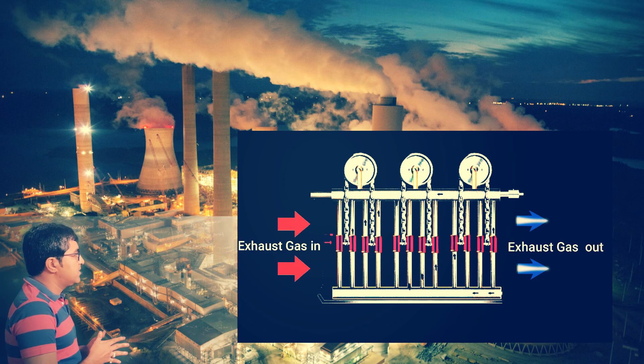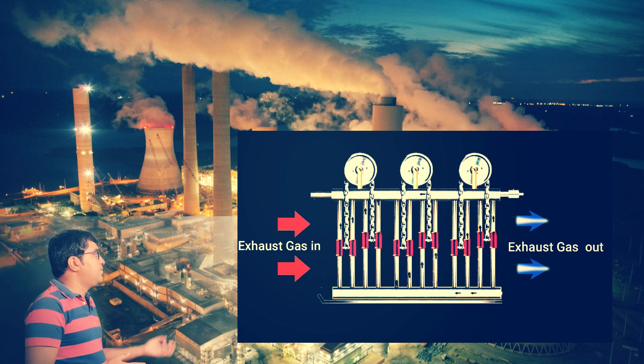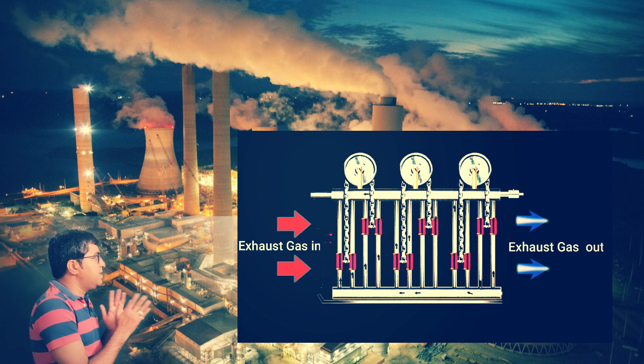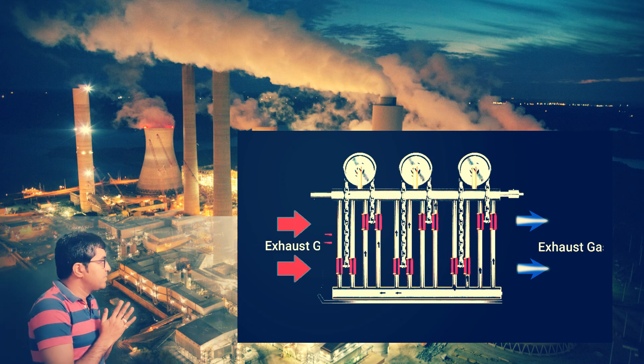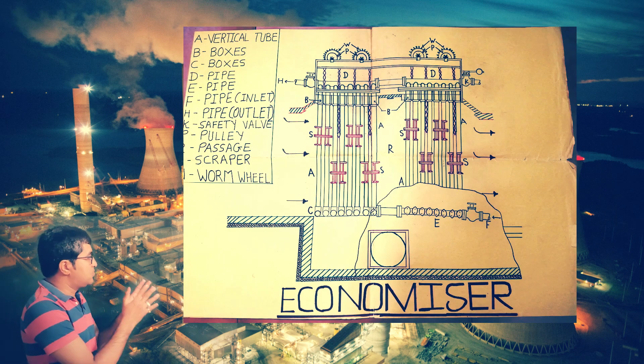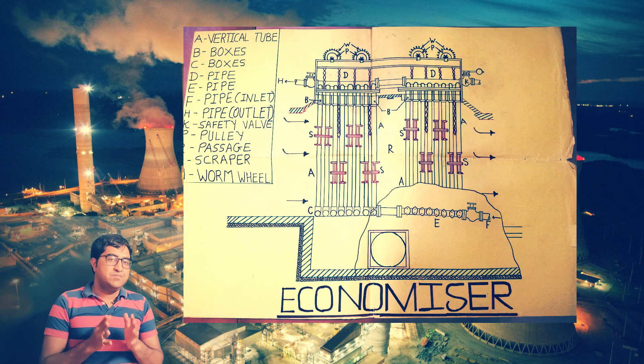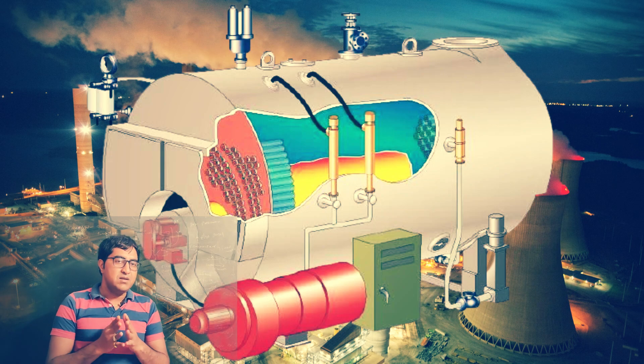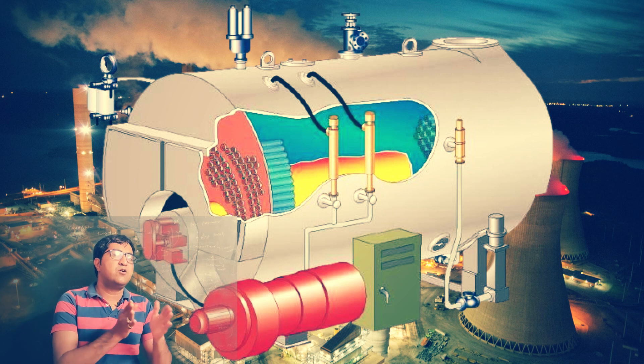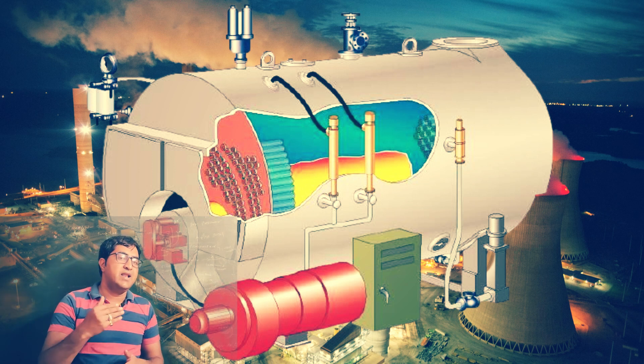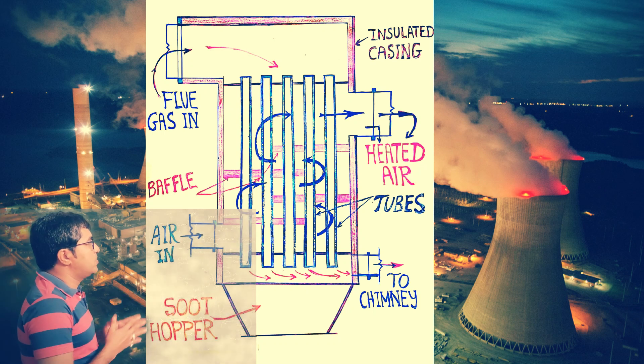In the economizer, water flows inside the tubes and the flue gases pass outside the bundle of tubes. This bundle of tubes exchanges heat between the water and the flue gases. Due to this heat transfer, the temperature of the water increases, and this hot water is supplied to the boiler. This component improves the performance of the boiler because preheating the water means less heat energy is required to generate steam.